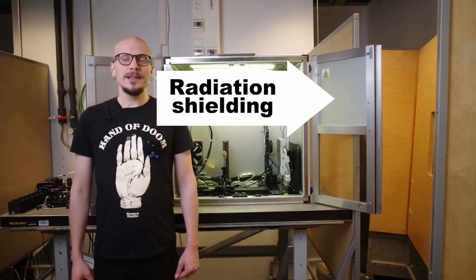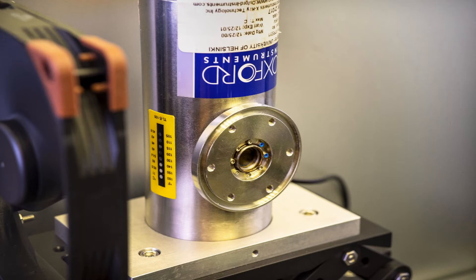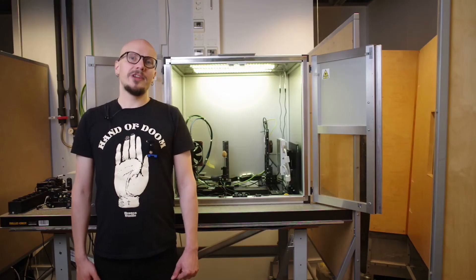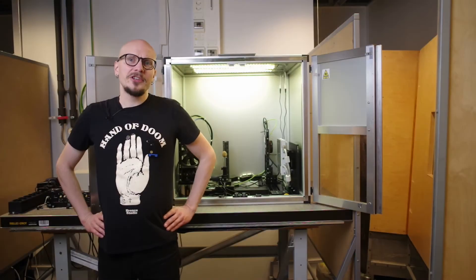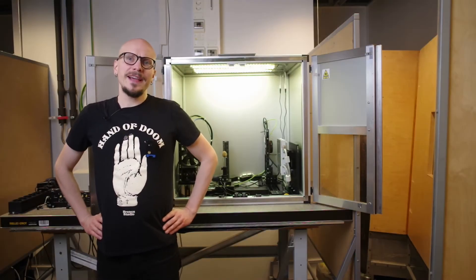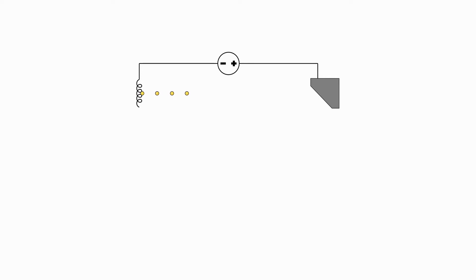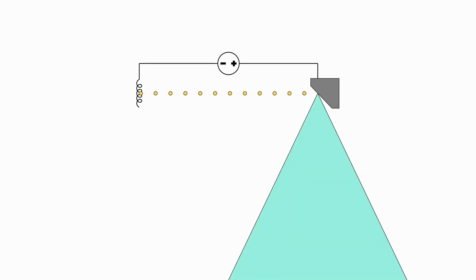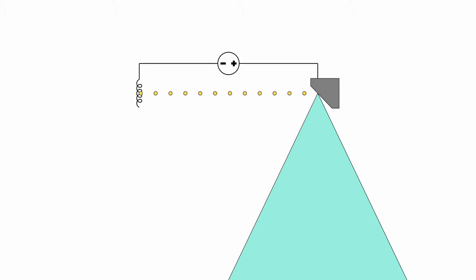This is the x-ray source, also called an x-ray tube. The cone-shaped radiation beam is emitted from the source through a thin beryllium window. So how are x-rays generated? An x-ray tube is a vacuum tube containing a cathode filament and an anode. The cathode is heated resulting in thermal emission of electrons. A high voltage is created between the cathode and the anode. The electrons emitted from the cathode experience a force which accelerates them towards the anode. In the resulting collisions with the anode, x-rays are emitted.